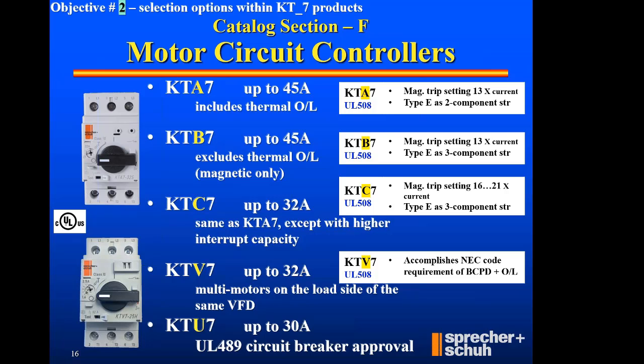Well, there might be a couple of circumstances. What if I got multiple starters and I needed a dedicated reset? Well, adding an overload and putting a remote reset module on the overload allows you a dedicated reset. Well, what if I needed some extra protection features such as thermistor protection or ground fault protection or something like that? Well, changing it to a KTB, adding a CEP7 overload, full featured overload at the bottom, and adding a protection feature to the side of the overload accomplishes that. So it kind of explains why a KTB7 exists.